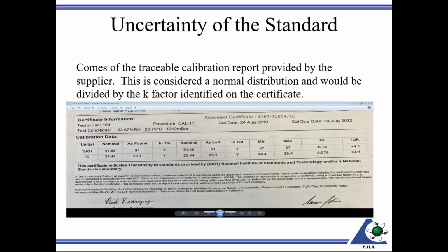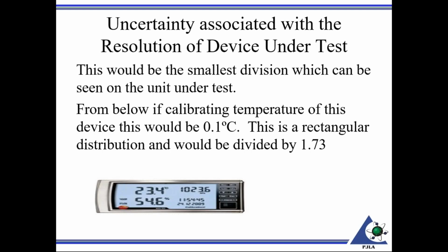So again, the uncertainty of the standard, the first one there, comes off the calibration report. So I have a sample here. We have a measurement uncertainty here. We have the K factor there, which you can read in the description at the bottom. If perhaps this temperature was a standard you were using to do temperature calibrations, you would take that measurement uncertainty of 0.676 and divide it by the K factor. That would be identifying and quantifying that particular uncertainty contributor.